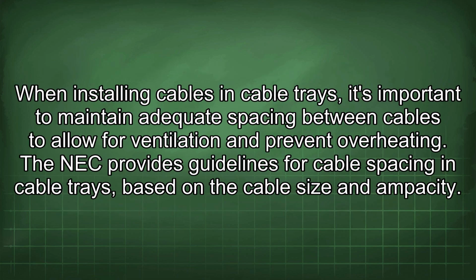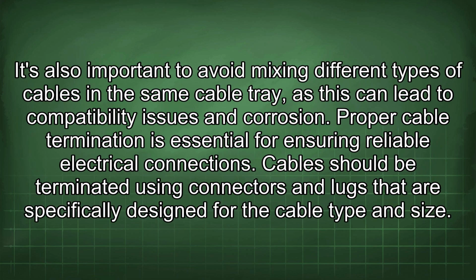When installing cables in cable trays, it's important to maintain adequate spacing between cables to allow for ventilation and prevent overheating. The NEC provides guidelines for cable spacing in cable trays based on the cable size and ampacity. It's also important to avoid mixing different types of cables in the same cable tray, as this can lead to compatibility issues and corrosion. Proper cable termination is essential for ensuring reliable electrical connections.